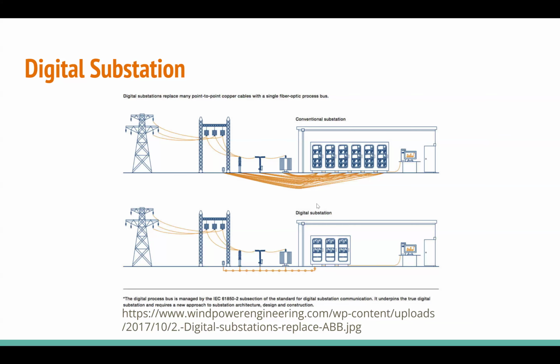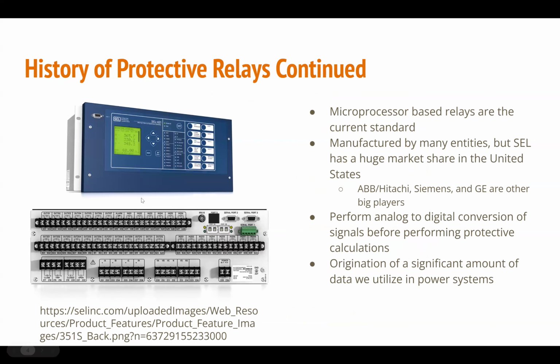Jumping back to this relay, what we can see here is current for our A phase, B phase, C phase, and neutral, and then voltages for A, B, and C. If we wanted to monitor multiple buses or lines at the same time, we'd need multiple of these inputs. With a digital relay, we just send all of it over one fiber optic connection. One relay can be monitoring 30 current transformers or 5, it doesn't matter, it's just one cable.